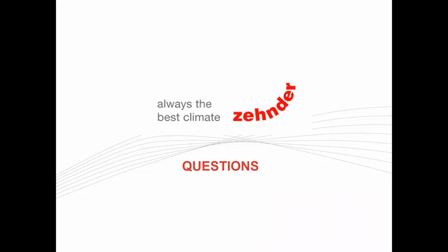Okay, thank you. Next, it says, it looks like the operating temperatures can accommodate geothermal equipment. Is that correct? Yes. So the source, however, the water temperature, the source that you're getting it there, from a radiant point of view, it doesn't affect me. But yes, geothermal, actually our facility up in Buffalo uses a horizontal geothermal loop underneath our parking lot to supply the chilled water and hot water to the panels.